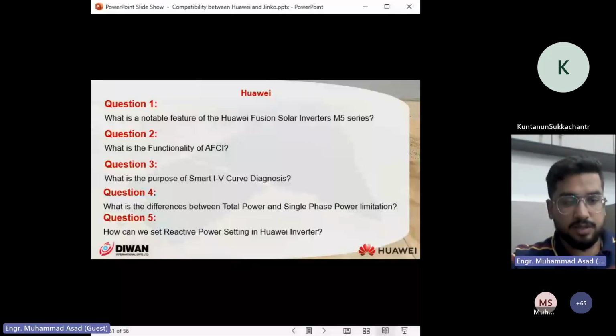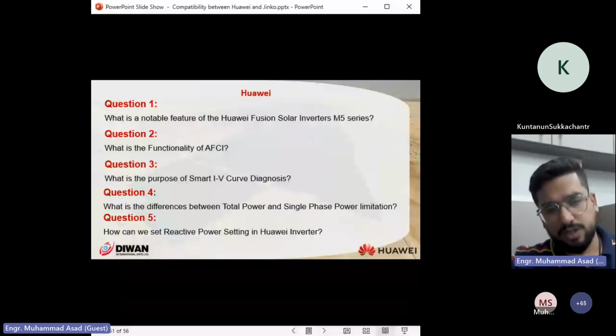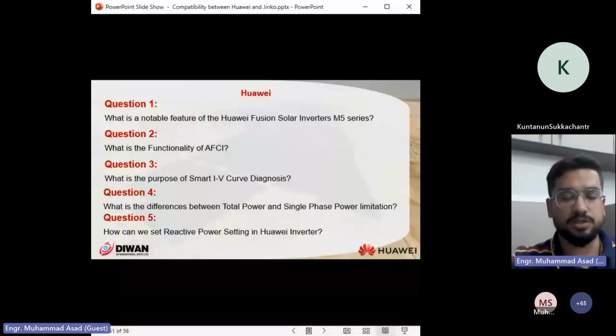The power limitation is the most important thing with Huawei. Installers really face trouble with it, and we mostly get complaints about total power or single phase power limitation. The power meter isn't working properly because they didn't follow the manual instructions correctly, and sometimes they install the CTs in the opposite direction, or there's a phase sequence issue.